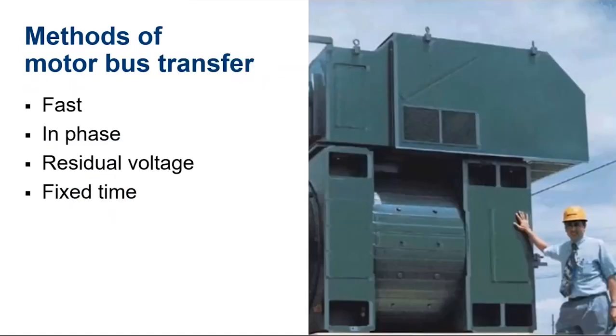There are four methods of bus transfer: fast, in-phase, residual, and fixed time. The first three, fast, in-phase, and residual, are all based on variable system conditions. And the last one, fixed time, is based on a set time delay. This is possible with internal logic. So you set a timer, and then as the timer expires, you do the transfer.